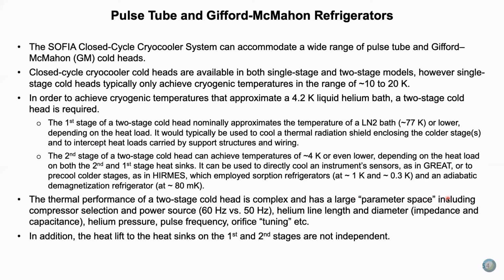The SOFIA cryocooler system can accommodate a wide range of pulse tube and Gifford-McMahon cold heads. Closed cycle cryocooler cold heads are available in both single stage and two-stage models. And looking at the third bullet, we really need a two-stage cold head. That's because the first stage of a two-stage cold head nominally approximates the temperature of a liquid nitrogen bath, 77 K or lower, depending on what the heat load is. Now, this would typically be used to cool the thermal radiation shield, which encloses the colder stages, and it's used to intercept heat loads carried by support structures and wiring.